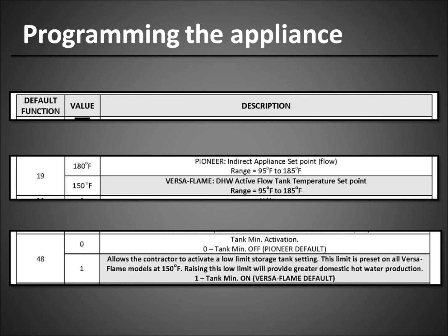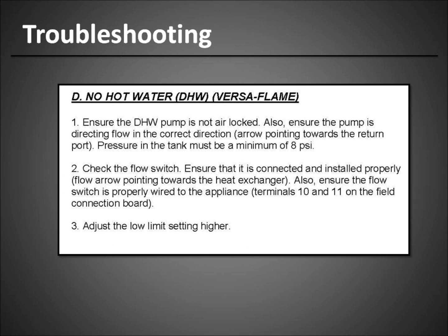Okay. And then just some of the troubleshooting. In some of our field installations, one job that I was involved in, they were supposed to have the system all bled and ready to go, but unfortunately they didn't. And one of the things that was happening is one of the gentlemen upstairs was bleeding one of the old cast iron radiators. And I lost pressure. I didn't know it on the gauge, and I was not pumping through the braze plate. And I found out that they had basically brought the pressure down to nothing.